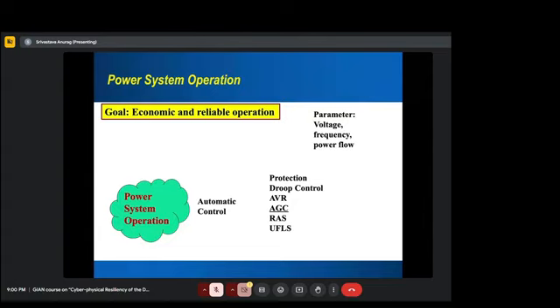In a few cycles it has to operate. Typically it has to detect the fault in half a cycle to one cycle, or maybe a little bit more than one cycle, and then it has to wait for a few cycles so that it does not mal-operate, and so it's the fastest automatic control. Then there's a droop control, right? And we are talking about those things that we have made.